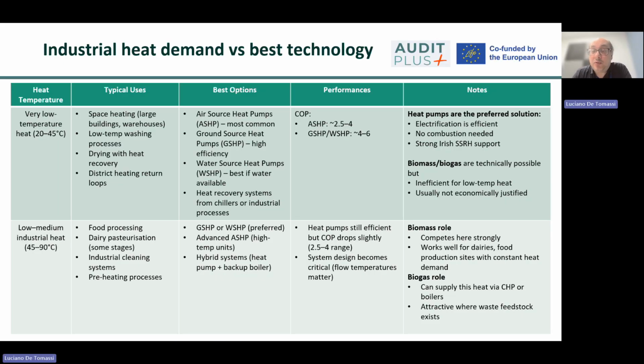Industrial heat demand is strongly linked to temperature level because the available technologies and their efficiencies change significantly as temperature increases. Lower temperature heat is easier to supply efficiently using heat pumps and recovered waste heat, while higher temperature applications increasingly rely on direct combustion, electric resistance, or specialized high temperature heat pumps with lower coefficient of performance. A practical way to understand technology selection is to match the temperature quality of heat with the most efficient available supply option. In this table, we assess industrial heat demand across different temperature levels, their typical applications, the most suitable technology options, and their expected performance.